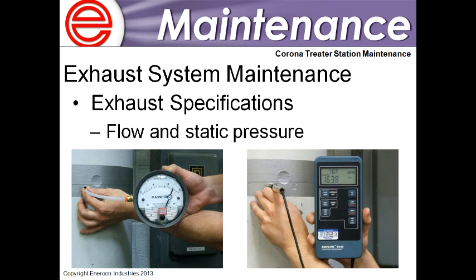And then the exhaust specifications. Again, it's the importance of that exhaust system to help remove ozone and heat from the electrodes to extend the life of your equipment. Again, this is something that either people have never done or they do frequently, and a lot of people I find have never done this. So it might be a good idea to go out and measure your exhaust duct airflow and static pressure. The Magnehelic is a differential pressure gauge shown on the left, which measures the static pressure. Most Corona treaters, wide web Corona treaters, the minimum static pressure is 12-inch water column. For narrow webs, it's about 7 or 8-inch water column. And then the airflow is going to depend on the size of the system and everything. If you have any questions about the minimum exhaust specifications for your system, feel free to contact me here at Enercon with the system serial number. I can help you out with that.